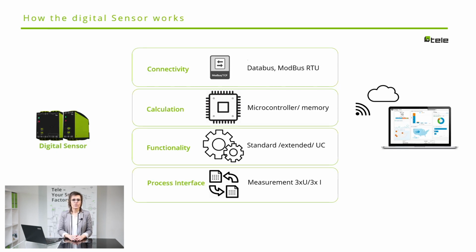The digital sensor measures simultaneously up to 3 AC voltage signals directly from the main supply and up to 3 AC signals via current transformers in real-time mode. Therefore, it is possible to generate RMS values and intelligent analytic data that can only be generated in real time, directly from the signal sources.